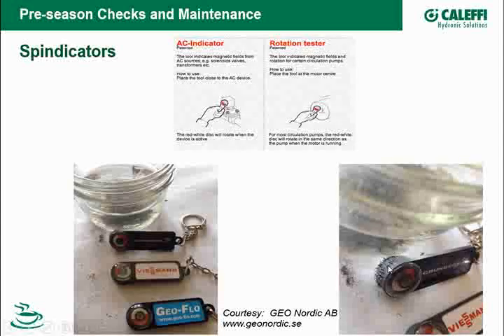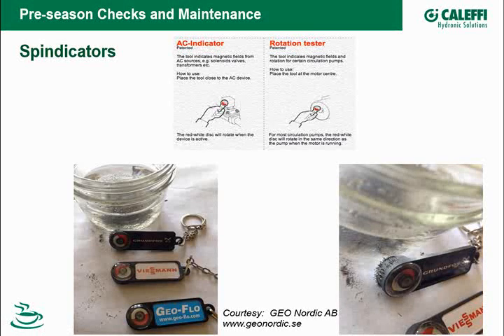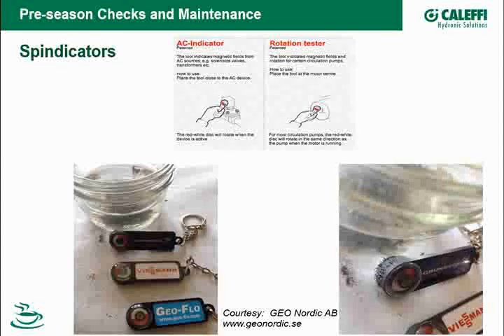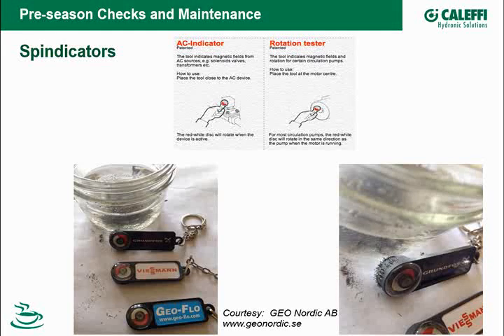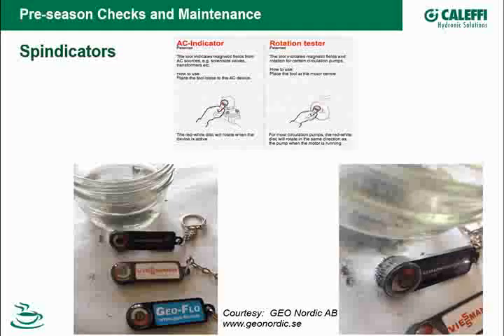And you're going to see that if you've got systems out there that have non-barrier tube, the old polybutylene systems, or maybe some of the early rubber tube systems that didn't have oxygen barriers in them, you'll get a buildup of this iron ferrite in there, and it looks almost like a talcum powder consistency of magnetic particles. If it sticks to a magnet, guess what? It's part of your system that's being dissolved, and it can settle out in tubes, it can settle out in heat exchangers and cause a problem. So use your spindicator to test your fluid sample too.